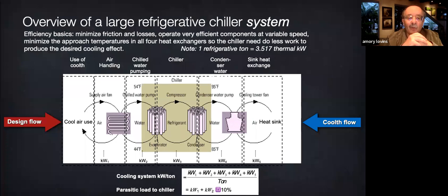The supply fan and chilled water pump heat ends up as extra parasitic chiller loads, making the chiller even bigger and using even more energy. Oh, by the way, is anybody wondering why the US unit of refrigeration is called a ton? It's the cooling done by melting 1 short ton, 2,000 pounds of ice. Because before Mr. Carrier's refrigeration machine, we bought ice by the ton from horse cart vendors who would saw it out of frozen northern lakes, ship it to the cities, and store it under insulating straw or sawdust. So the number comes from the latent heat of fusion of water, 80 calories per gram.